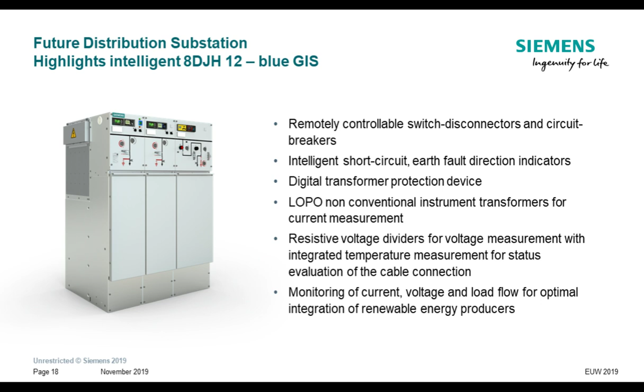Additionally, we have integrated temperature measurement in these resistive voltage dividers to give also the status evaluation for the cable connection. This means we can measure via the temperature or give predictive information about the status of the cable connector. As soon as the temperature is increasing, while the loads and the ambient temperatures stay stable, there is an information that something is wrong with the cable connection. So this is also installed in these 8DJH 12 Blue GIS switchgear.